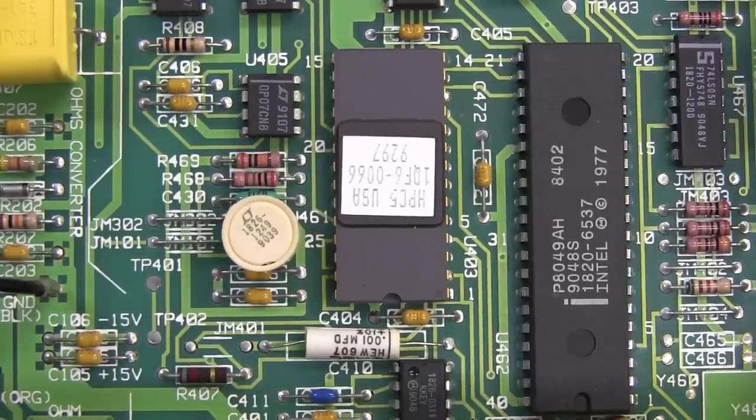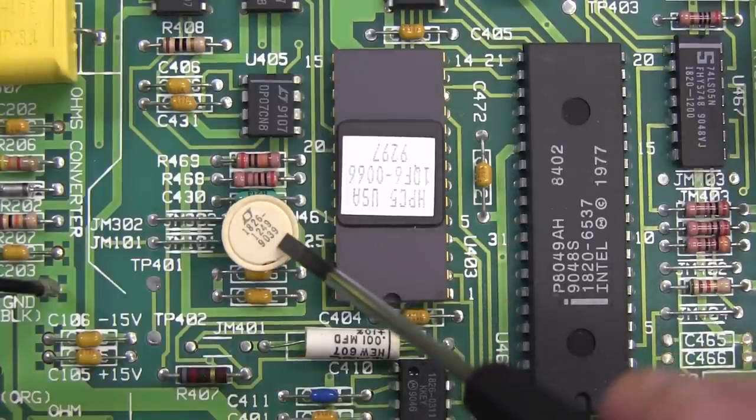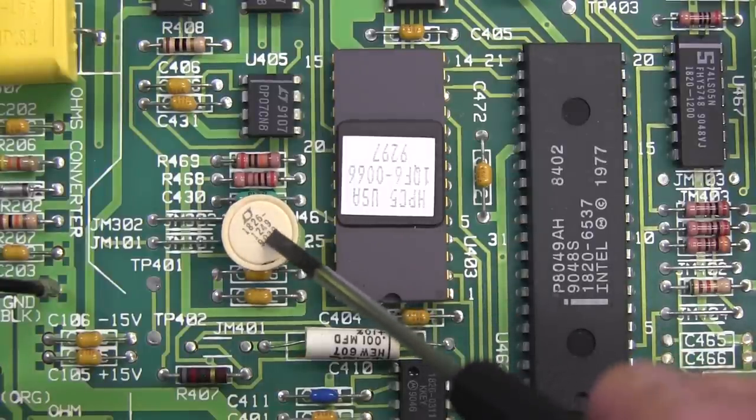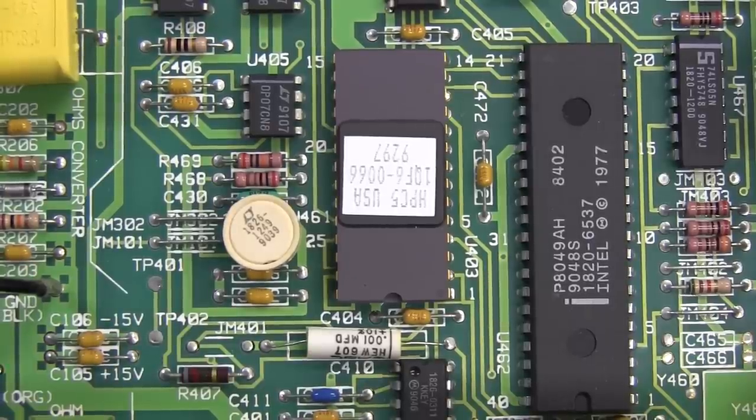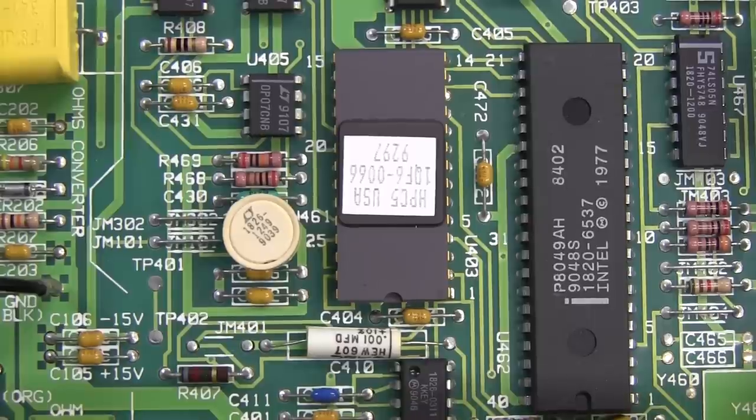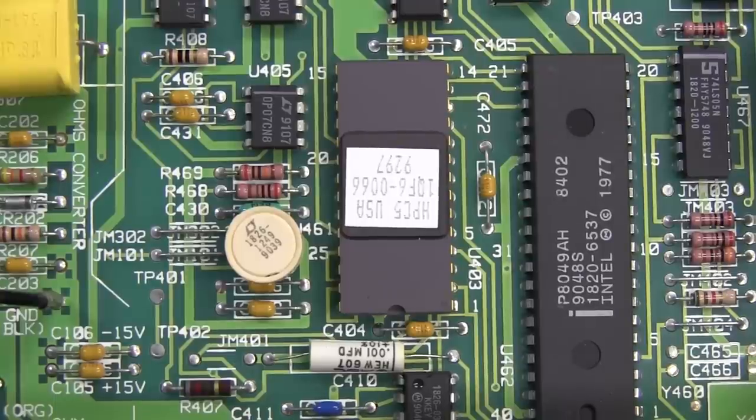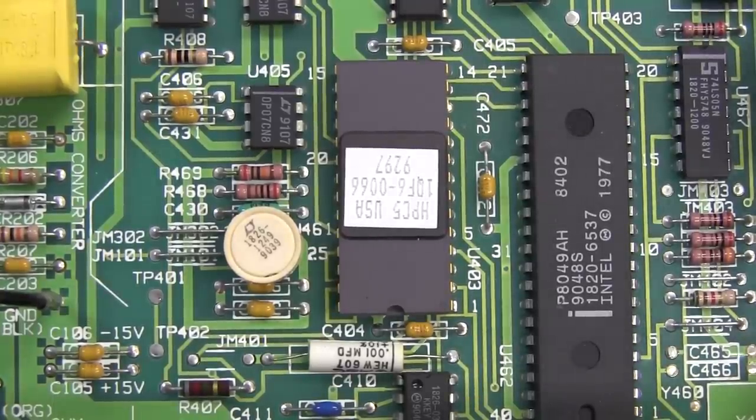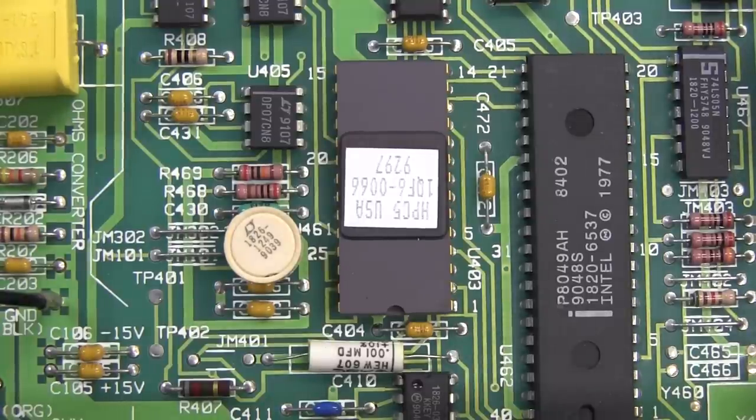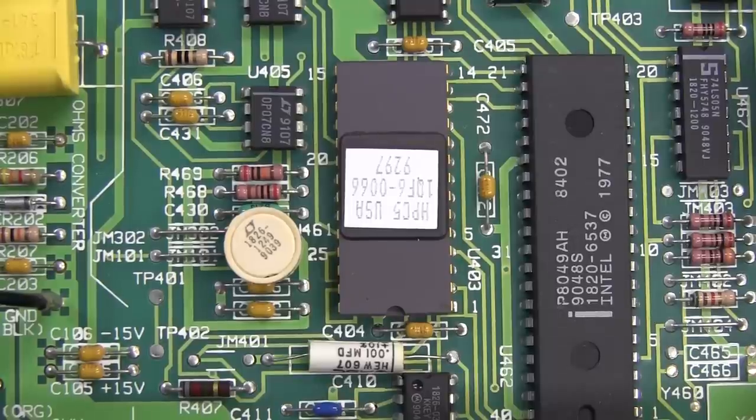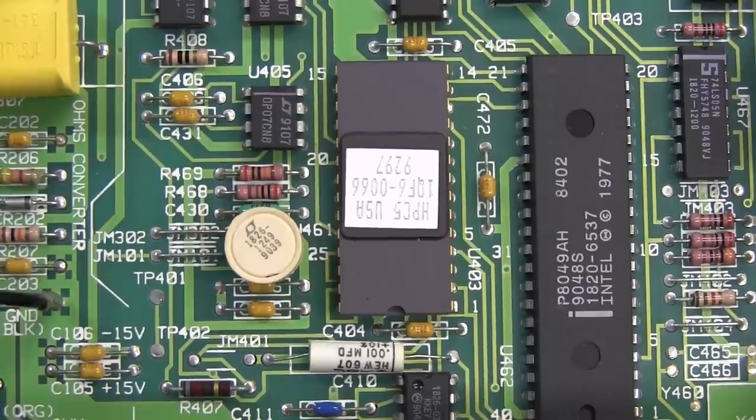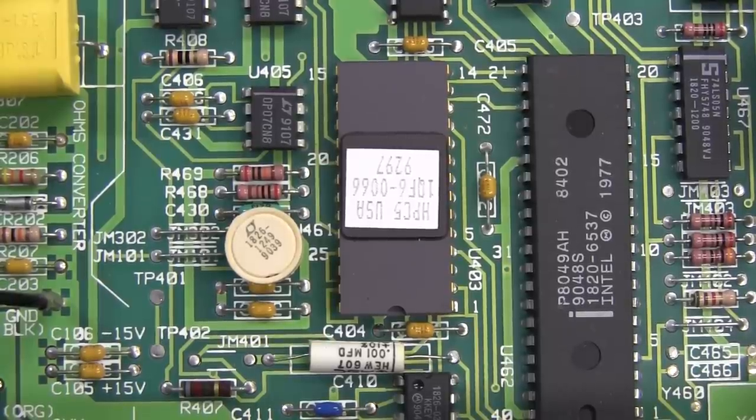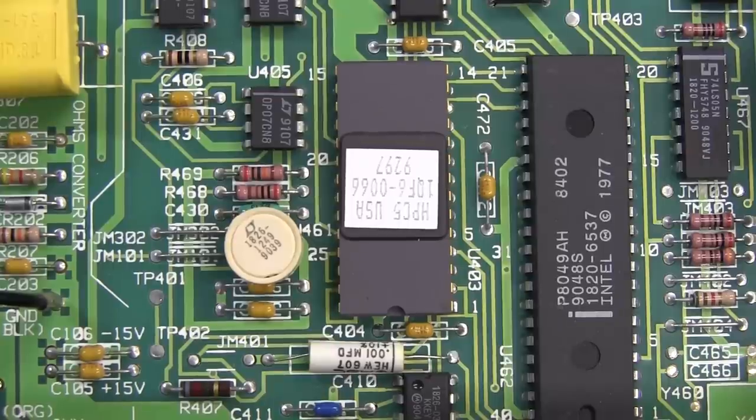And of course the voltage reference, absolutely identical linear technology. It's got the HP part number, but as we found out that is a linear technology LM399. So exactly the same voltage reference. I presume it's the same grade that's used in its big brother. So the specs are going to be very similar, if not identical, to its big brother. I think they are slightly different in some respects, but not by a huge margin. That's why, if you don't need the extra-digit resolution, and you don't need the math functions, this 3478A is a really great precision meter.